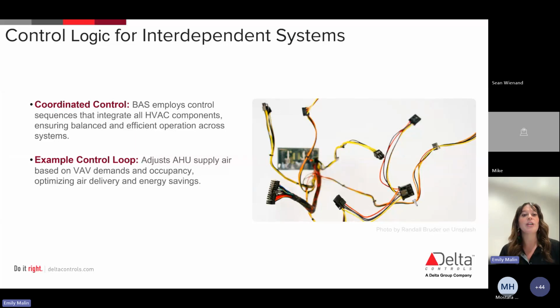So what we have on here is our example control loop. In real life, what this looks like is, say, in a particular room, a VAV system is going to signal to our air handling unit to adjust the supply air. This is going to trigger that control loop. And it's going to modulate airflow and create that temperature change based on real-time data to meet that set point without wasting energy.